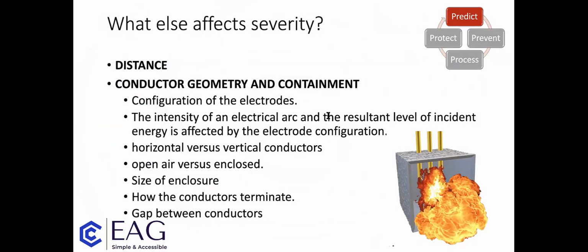The other thing that affects severity, I might just mention there are other things that I'm not going to talk about today, such as motor contribution and things like that, so forgive me on that one. But the other points that affect severity is the distance from the arc source, and it's an inverse exponential relationship. In other words, small increases in distance can drastically reduce the energy level. And the intensity of an electric arc and the resultant level of incident energy is then affected by the electrode configuration. You can see on the right-hand side, I've just put one of the 5 electrode configurations, which is arc in a box, basically. That's VCB, vertical conductors in a box.